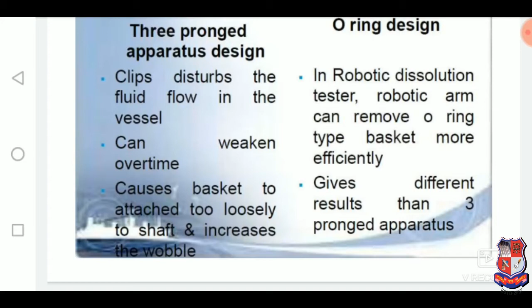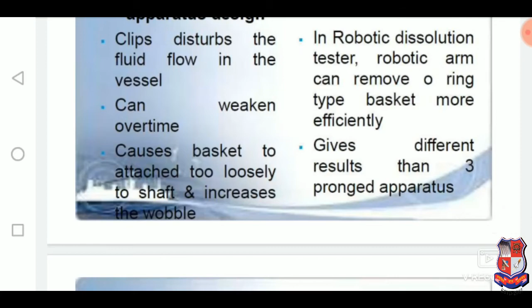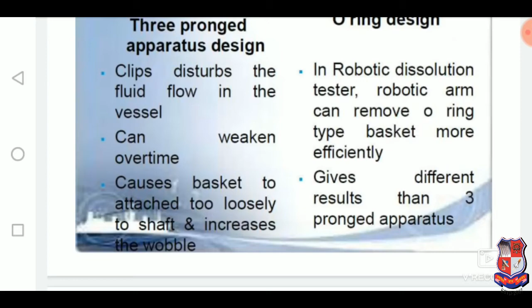Now in the O-ring, the robotic dissolution tester's robotic arm can remove the O-ring type basket more efficiently, and it gives different results than the three-prong. So why is there a different result? Because there is a flow in that clip type of design. So these are the requirements. The O-ring is widely applicable because it has no kind of flow produced from those disturbances.